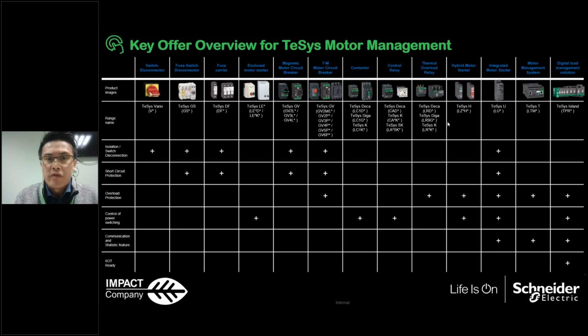We also have very good products for integrated motor starters, which we call TeSys U. You may be aware of that. It integrates the motor circuit breaker, the contactor, and the overload relay together. So it is one combined, integrated solution for customers, and it also communicates to the system. Besides that, we also have a smart motor management system, the intelligent MCC overload relay we call TeSys T, and also a digital load management solution with TeSys Island. Today I will focus more on TeSys Island, an innovative digital load management solution, and how we can run the site and the motors in a smart way.